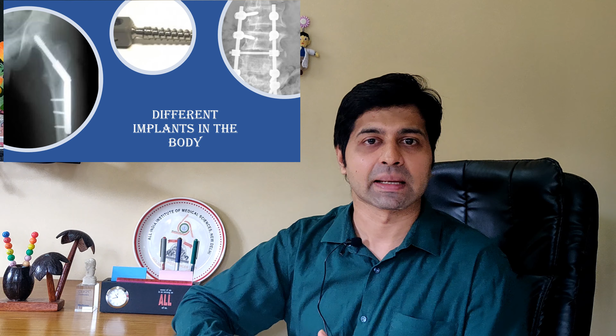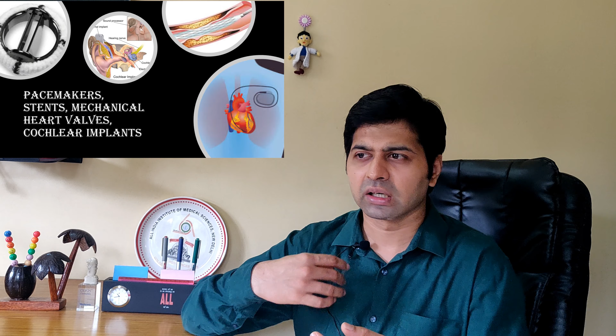This strong magnetic field can affect a patient if he has some magnetic or metallic thing implanted in his body, like the implants used for fixing fractures, such as screws, rods, plates, etc. Most of the implants which are used these days are made of titanium, which are MRI compatible, but if they are made of steel, then it could be problematic. Apart from implants, a few other things like cardiac pacemakers, stents, heart valves, and cochlear implants may get affected. They may get heated up, they may get displaced, or sometimes they may even get pulled out of the body towards the machine, causing a great amount of damage to the body organs.